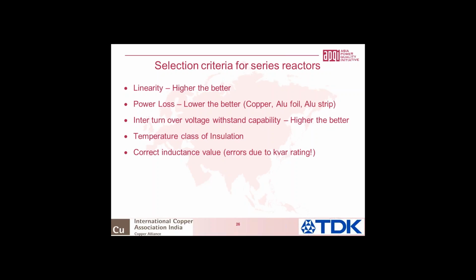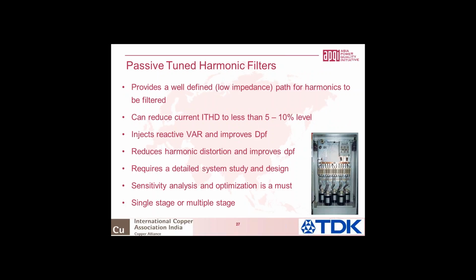Now, the other two solutions after the detuned or partially tuned solutions: we have fully tuned passive harmonic filters, which can reduce the current distortion to as low as maybe 5, 6, or 8, 10% level, depending on your system impedance and your frequency swings. This can inject VAR at fundamental frequency, by which it can improve the displacement power factor. It can reduce harmonic distortion. There are systems I have built where I could reduce current distortion from as much as 50-60% to as low as 8%. That means it can improve the distortion power factor. And of course, it can be single stage, multi-stage, single tuned, or multiple tuned.